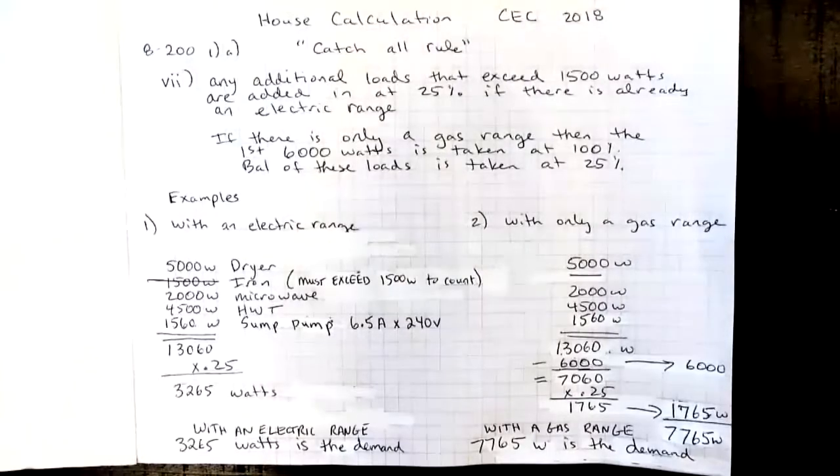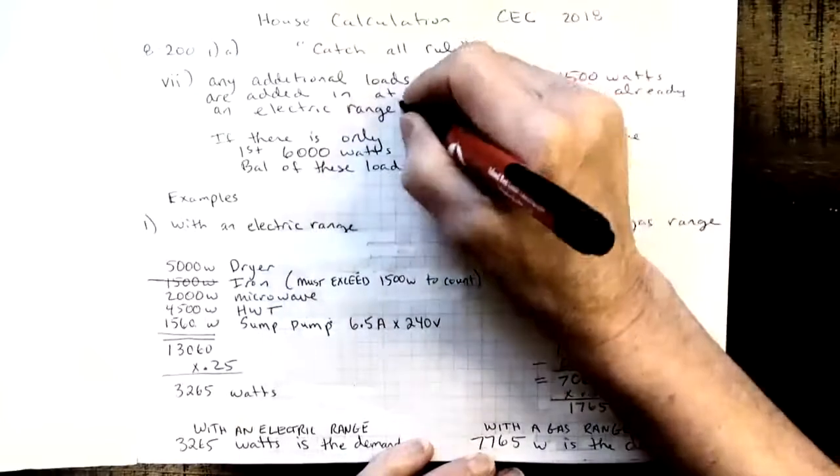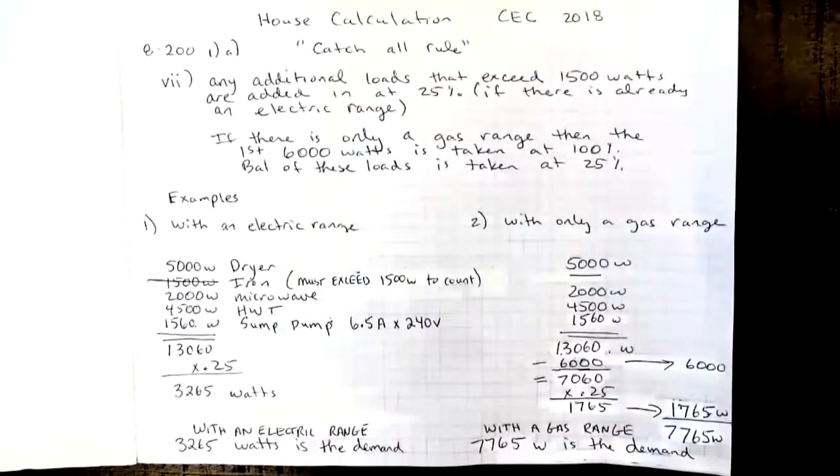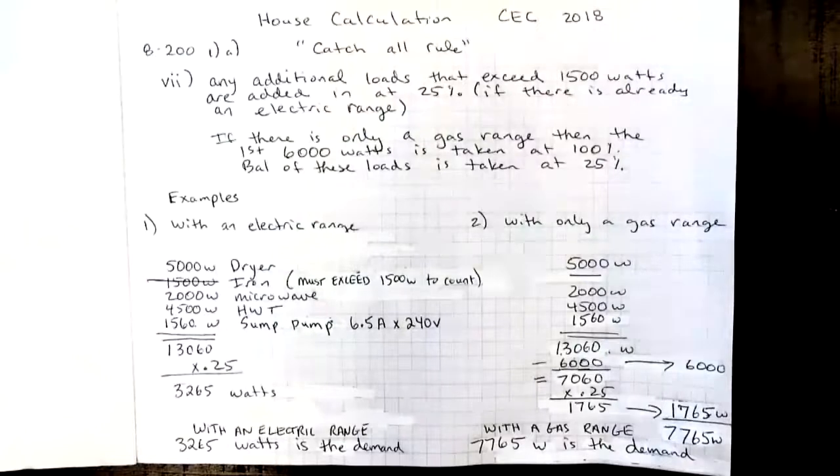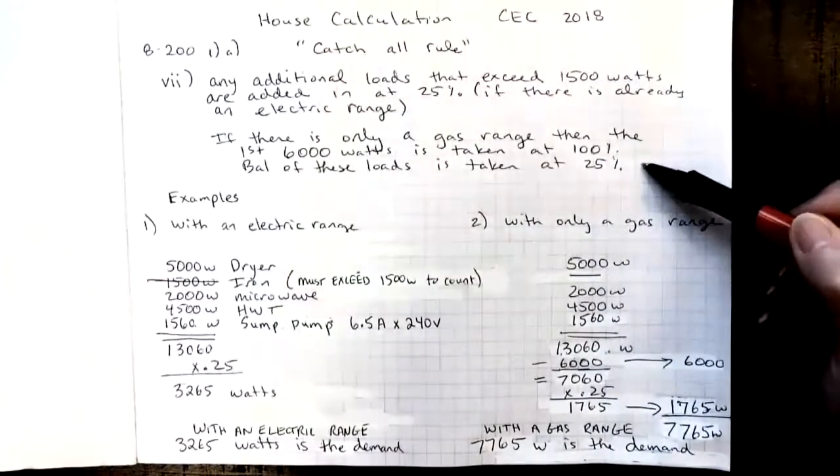Item 7 says any additional loads that exceed 1500 watts are added in at 25%. Now this is if there's already an electric range. If there's only a gas range, then we take these loads, add them up, and the first 6000 watts is taken at 100%, and the balance of these loads is then taken at 25%.